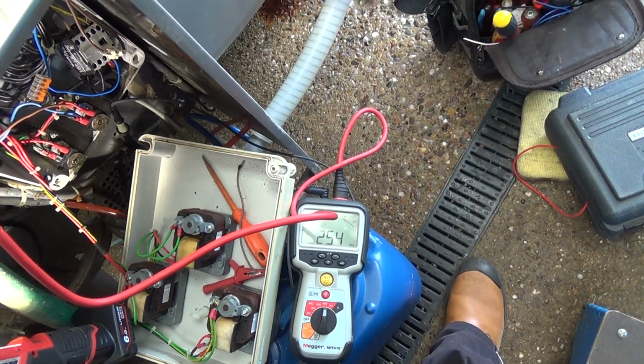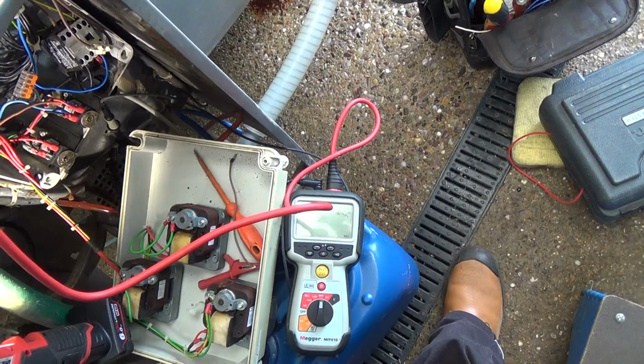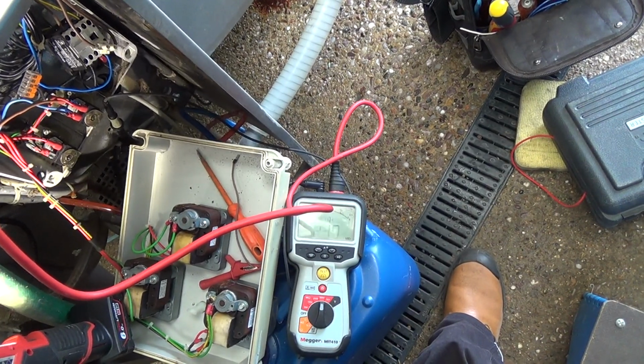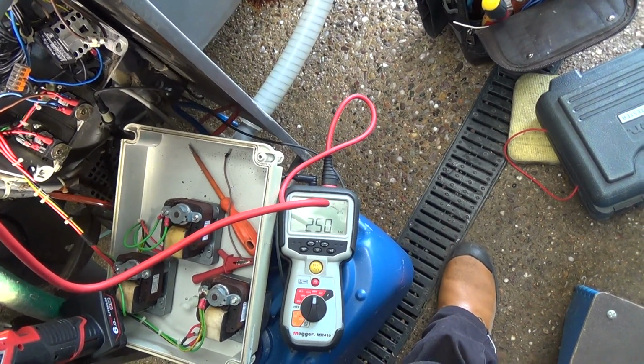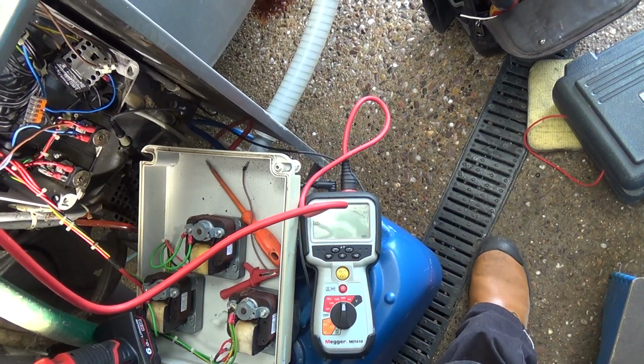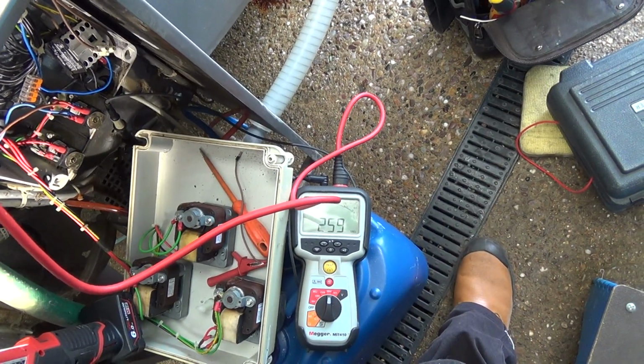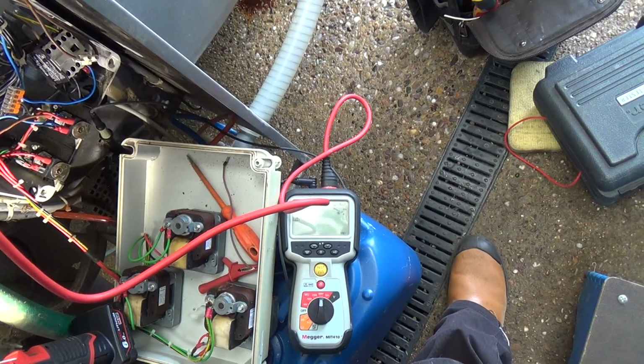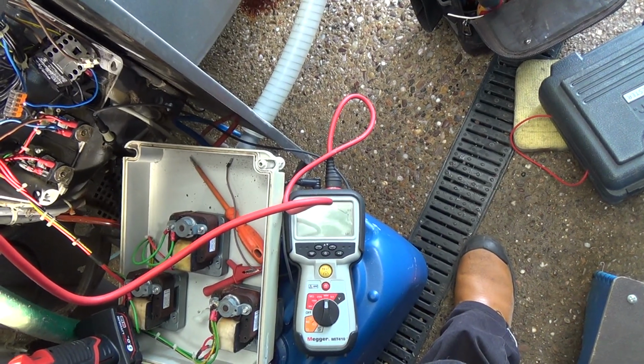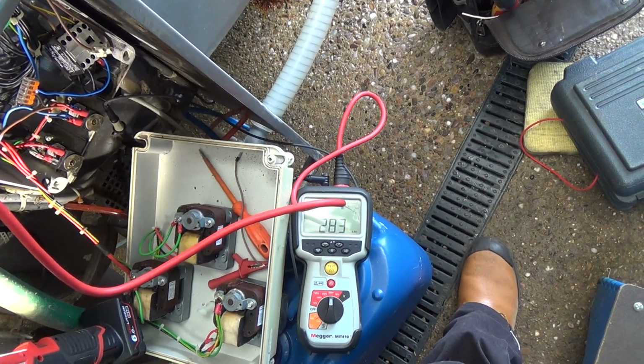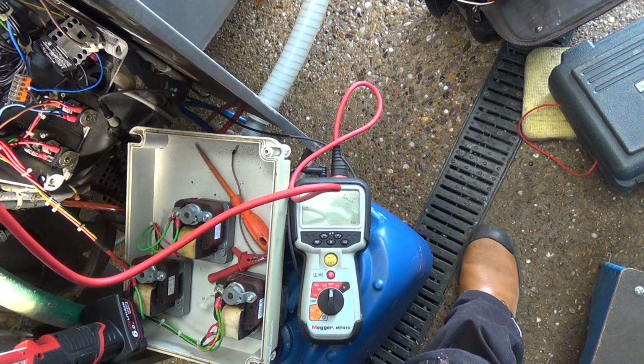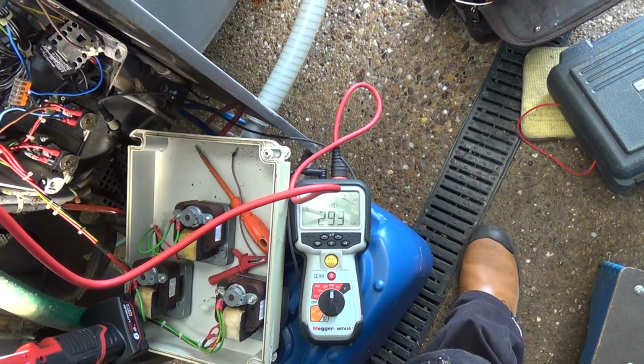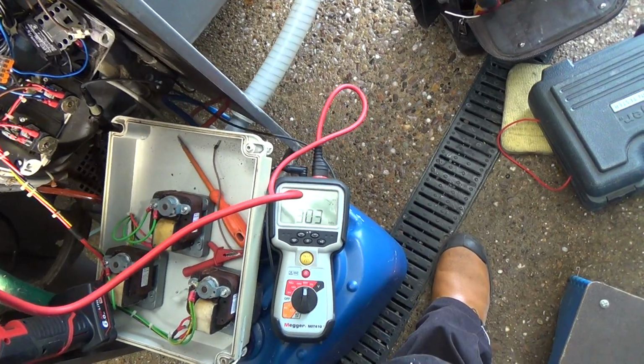So we're just testing all of these. It's about 250 megohms, which is nowhere near earthy enough. I mean, even at 1 megohm it would probably run without knocking the trip out, but there would be something, like if something was damp, which would dry out. If there wasn't dampness and something's reading 1 megohm, it's knackered, could have carbon tracking in there or something.